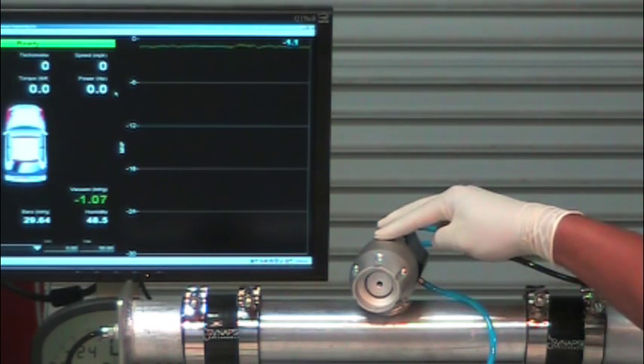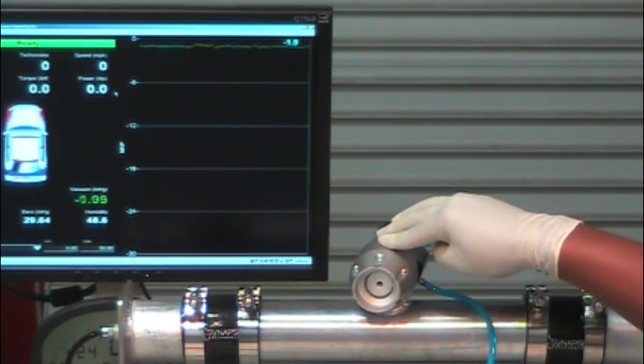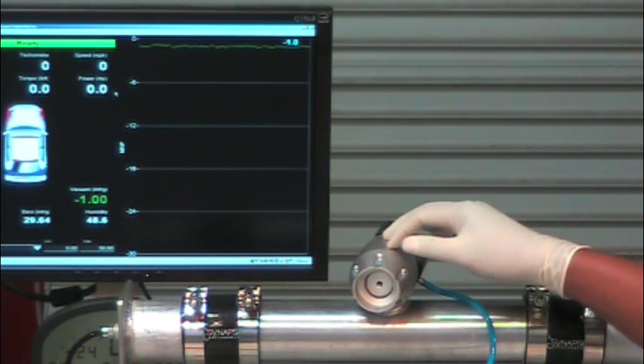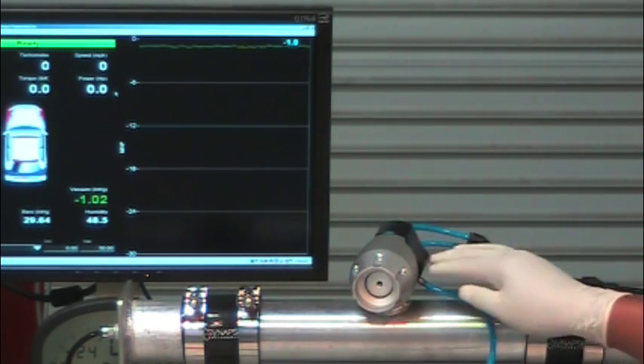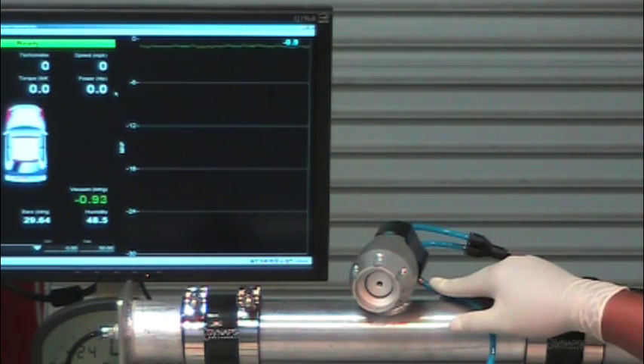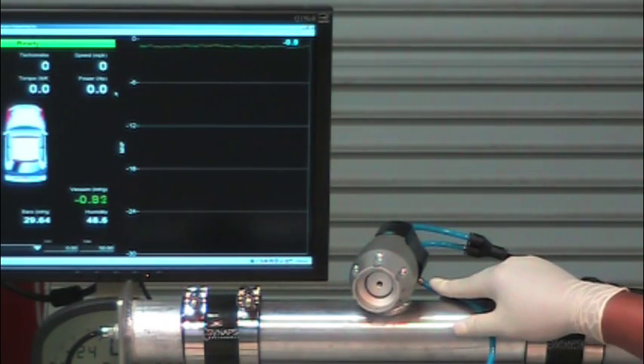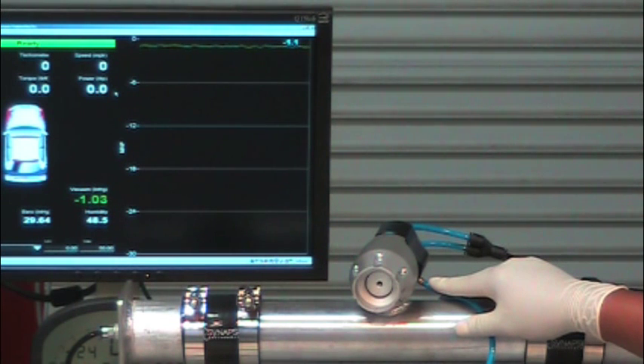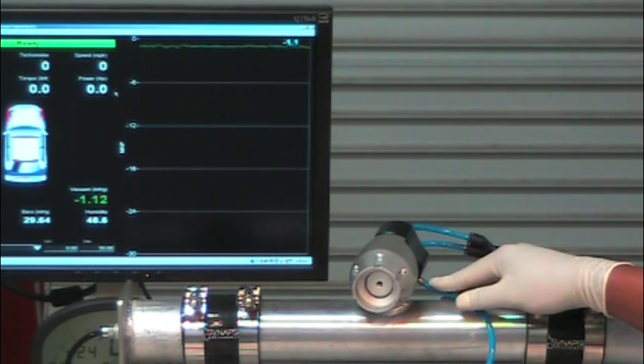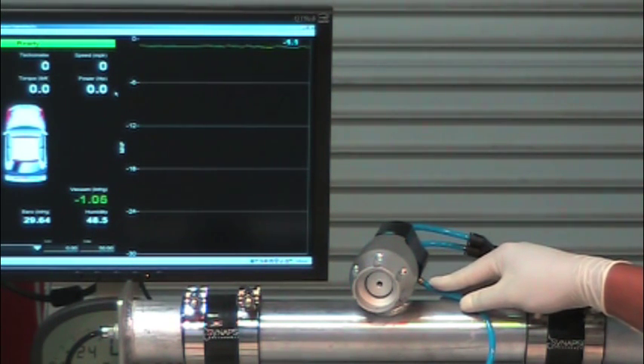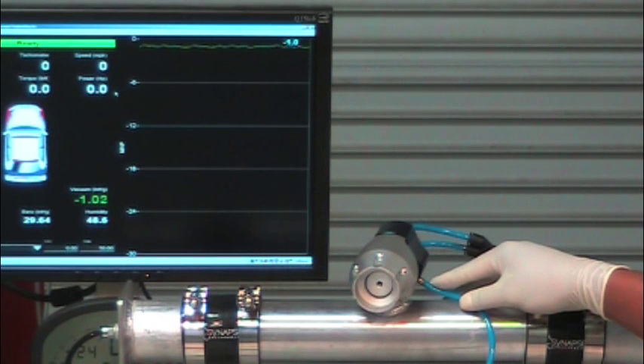This pressure relief valve is characterized by O-ring seals all the way around. So currently we're running relatively low pressures in it, such as 37 psi, but it can take burst pressures of up to 2,000 psi with a properly specced O-ring.